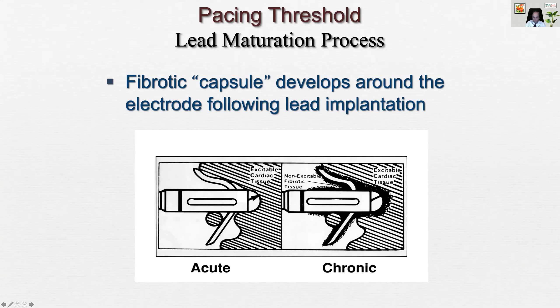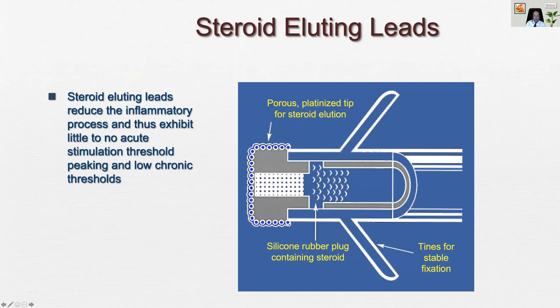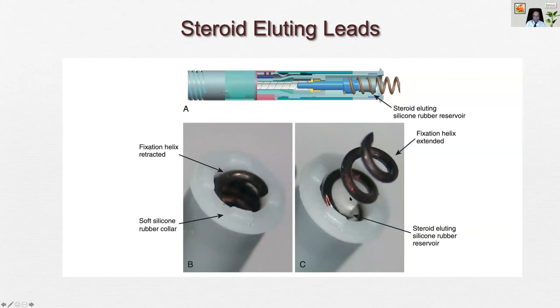That is, they have a steroid pocket inside the tip, which keeps on releasing steroid, usually dexamethasone, and which minimizes the amount of fibrosis. Even screw-in leads have a silicone rubber reservoir which contains steroid and keeps on releasing, and that improves the overall pacemaker lead maturation. So this used to be the situation about 25, 30 years back: after implantation we find a very good threshold, and after 1 week, 2 weeks, 3 weeks, often the threshold will rise to 2 volt, 3 volt, and then it will start to fall and settle at a level between 1 and 2, which was considered a very good threshold. But now with steroid eluting, it has become an almost flat curve, and the patients have very good pacemaker threshold throughout.